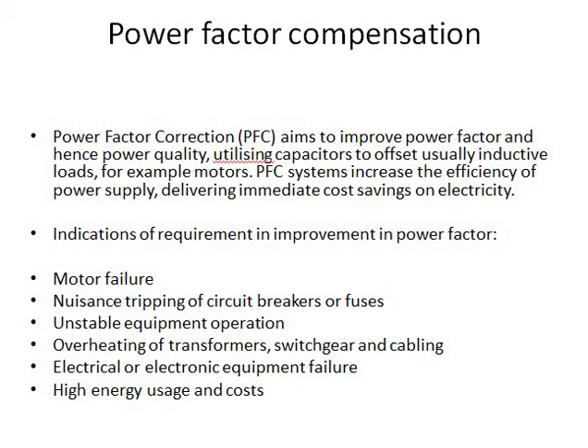Now, there are certain indications which a power system engineer or technician can get, which are a clear indication of a low power factor. Some of the indications may be motor failure, the motor not taking its rated speed, working abnormally, and overheating.